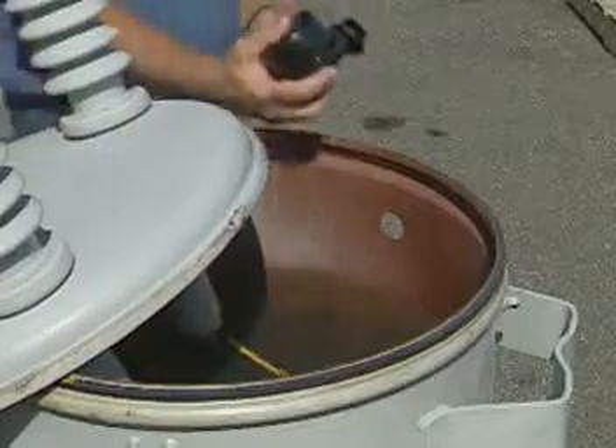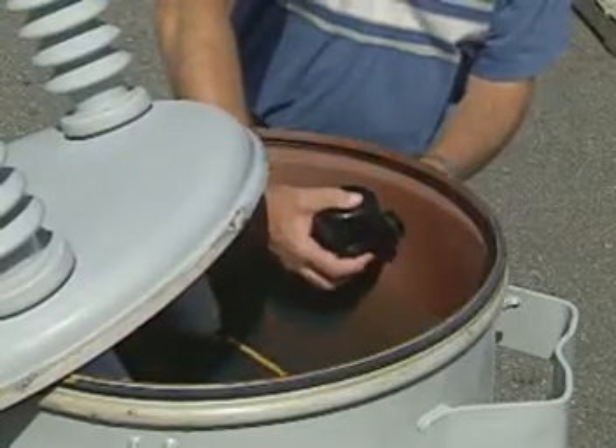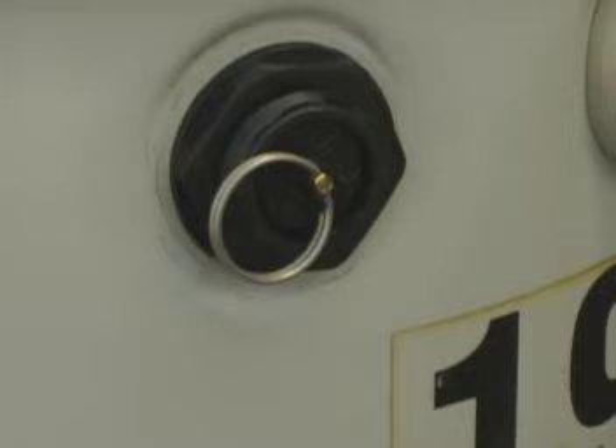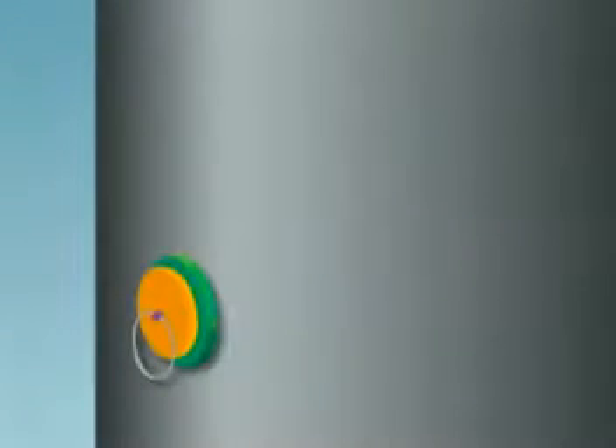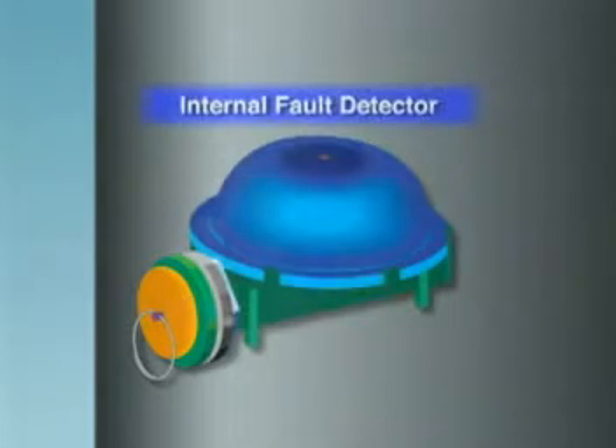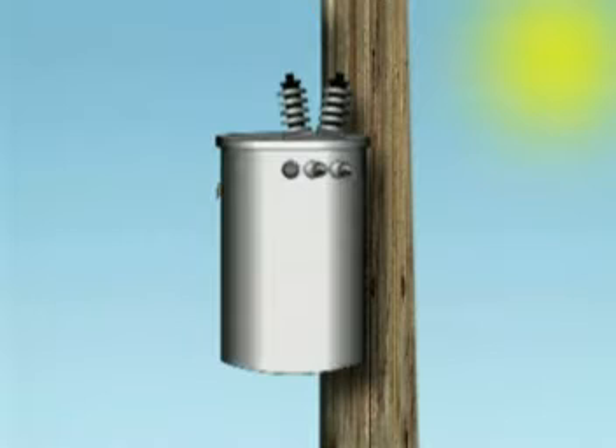The IFD is installed on the side of the transformer, above the oil level, and does not interfere with any of the electrical components inside the transformer. This graphic shows an IFD sensor. It is a purely mechanical device requiring no electrical connections. The IFD serves a dual purpose, as a pressure relief device, or PRD, and as a fault detector.